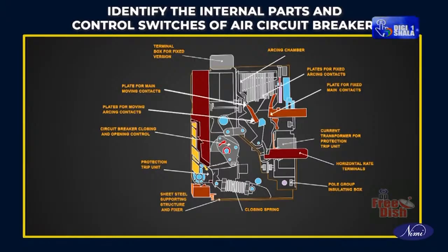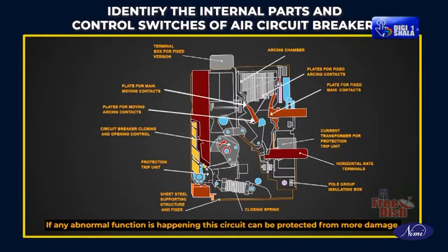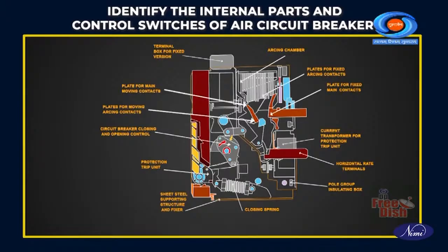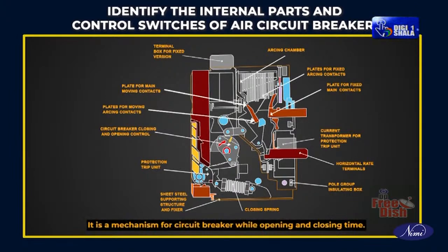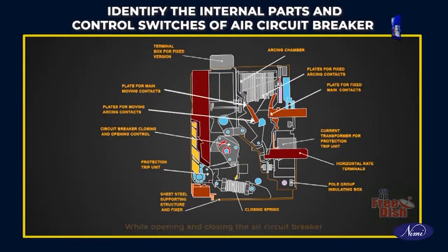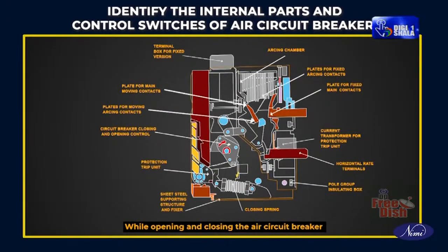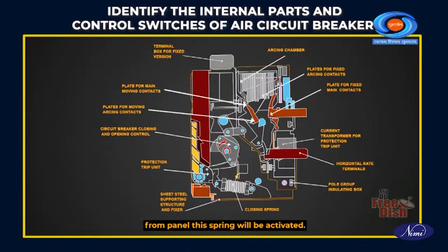Protection trip unit: if any abnormal function is happening, this circuit protects from more damage. Circuit breaker closing and opening control: it is a mechanism for the circuit breaker during opening and closing. Closing spring: while opening and closing the air circuit breaker from the panel, this spring will be activated.